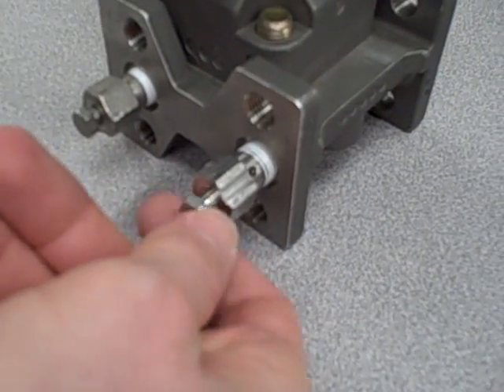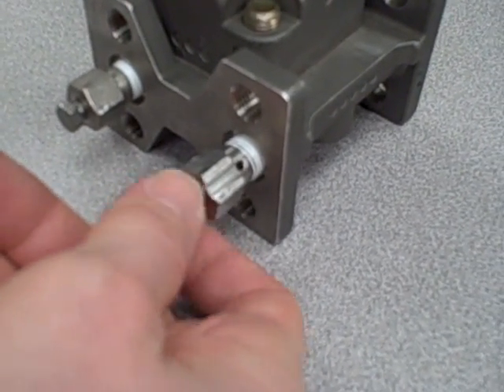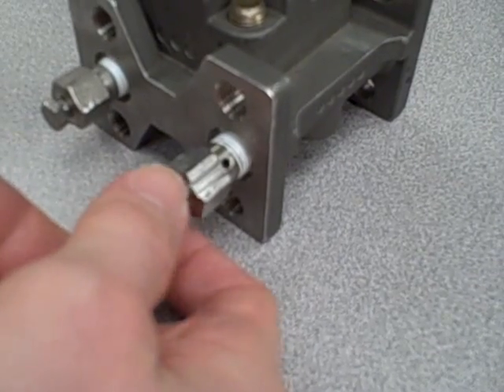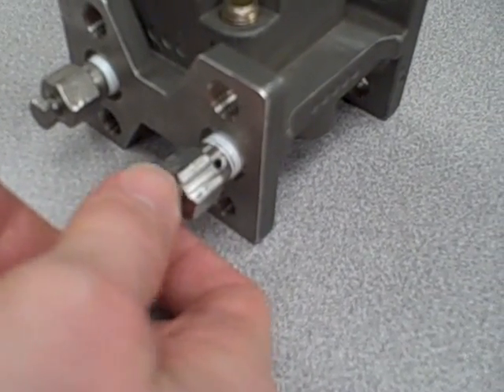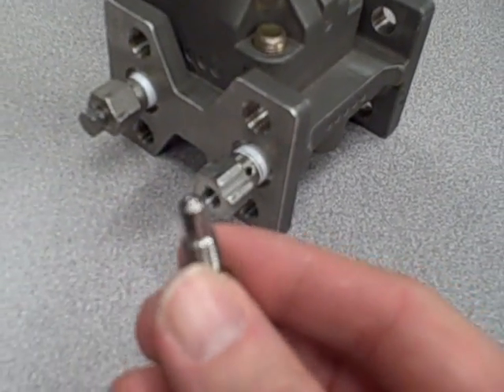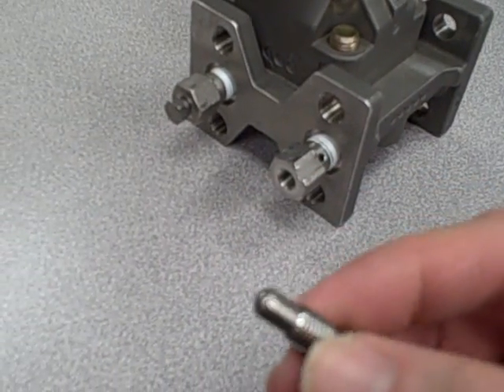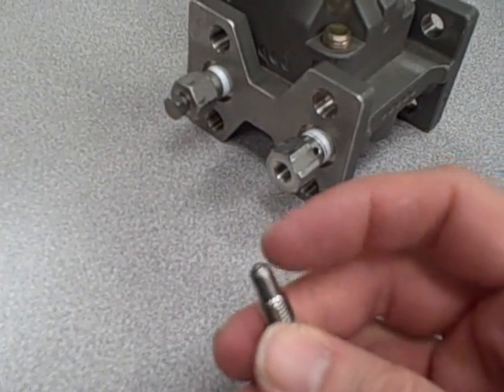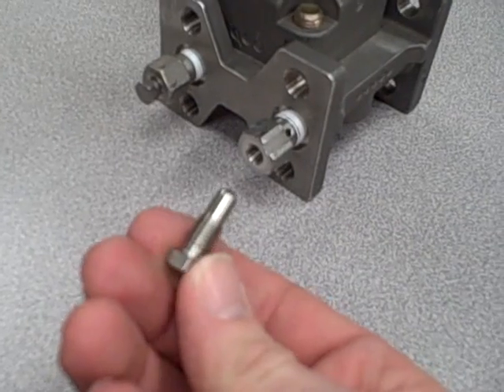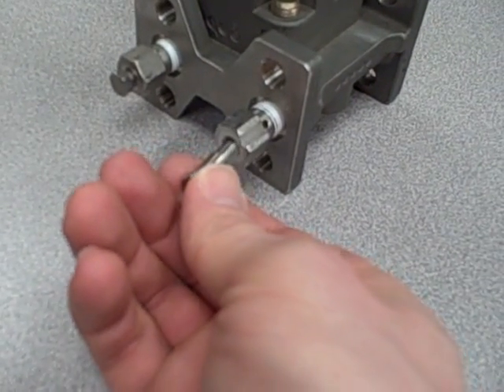And then it also has this part of it that is removable. I've made it hand tight with a wrench so I can take it out with my fingers. If we take that portion out and we take a look at it, what we notice is a little ball bearing at the end of this that is pressed into a seat as this plug is threaded into the bleed assembly.